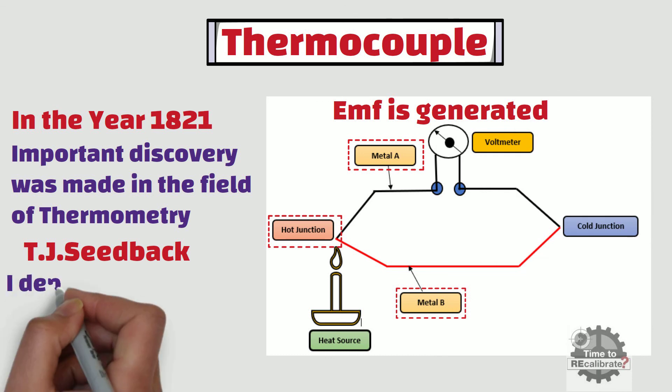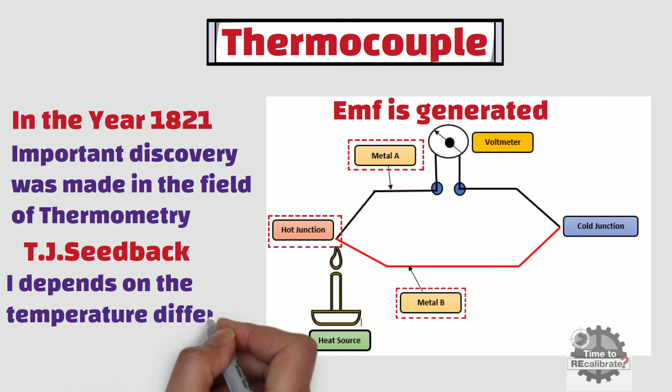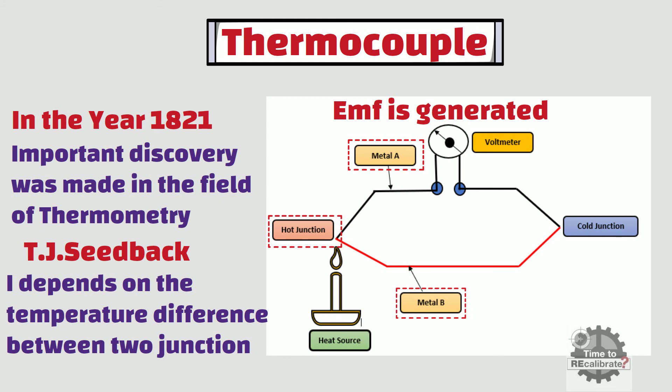The amount of electric current flowing in the loop depends on the temperature difference between two junctions. So if the temperature of one junction is kept at a known value, the temperature of the other junction can be determined by the amount of voltage produced. This discovery resulted in the temperature sensor we know as the thermocouple.